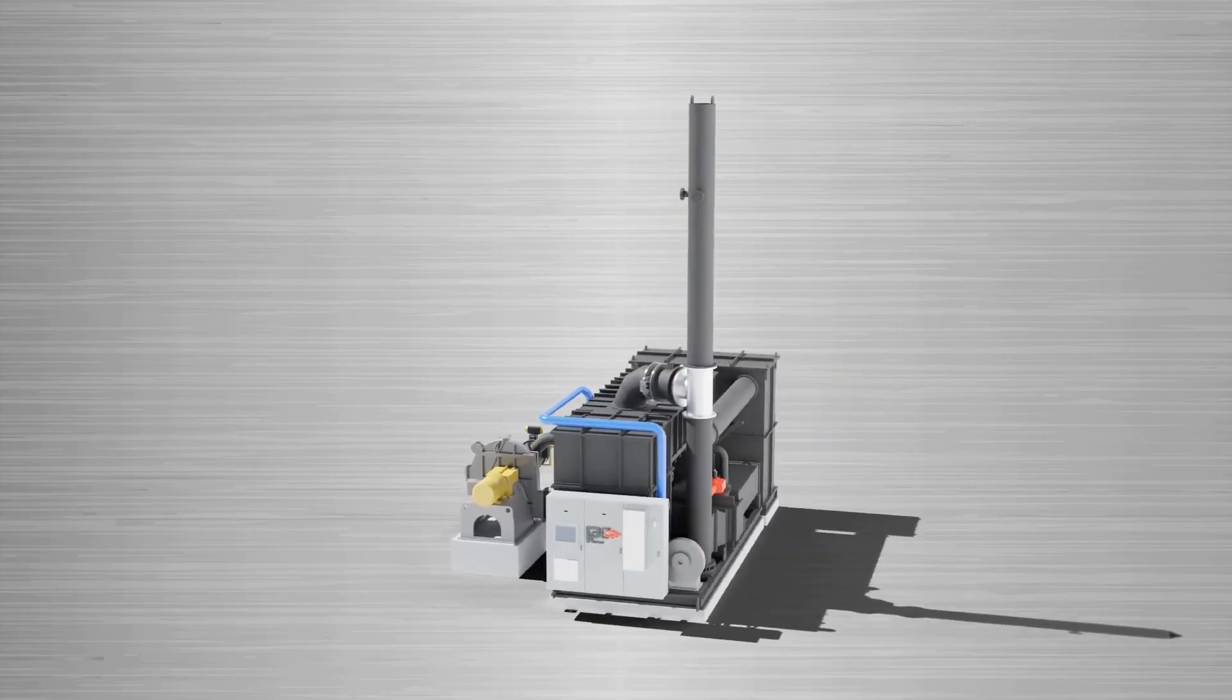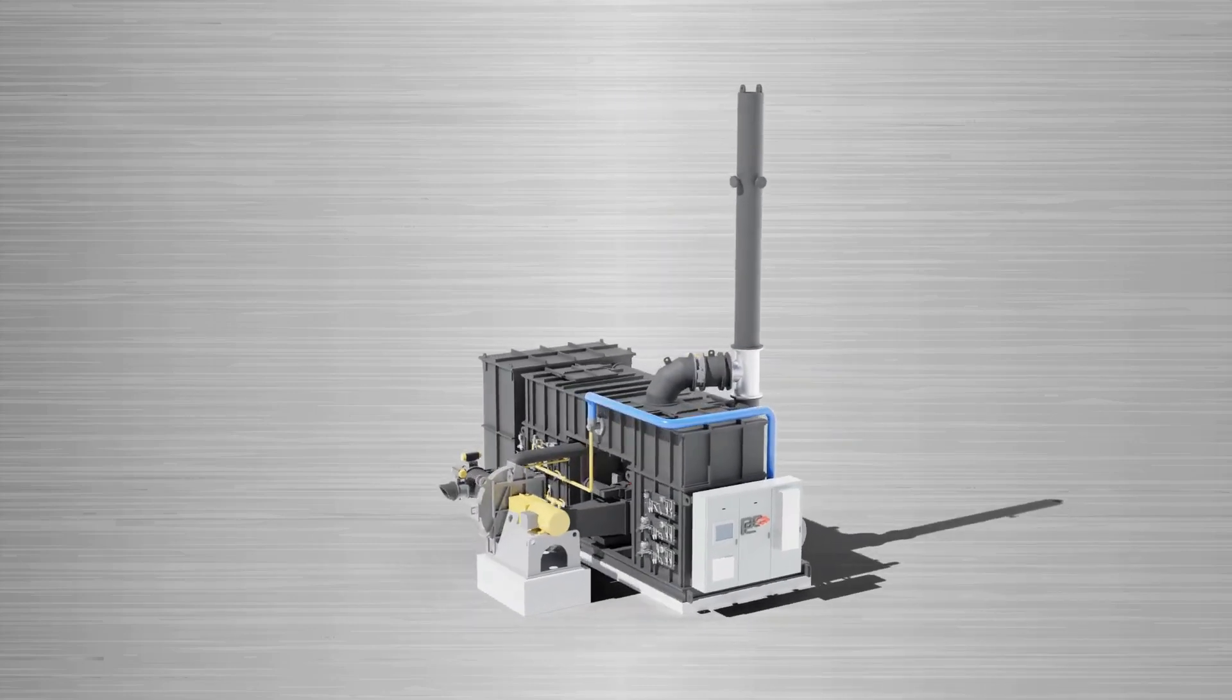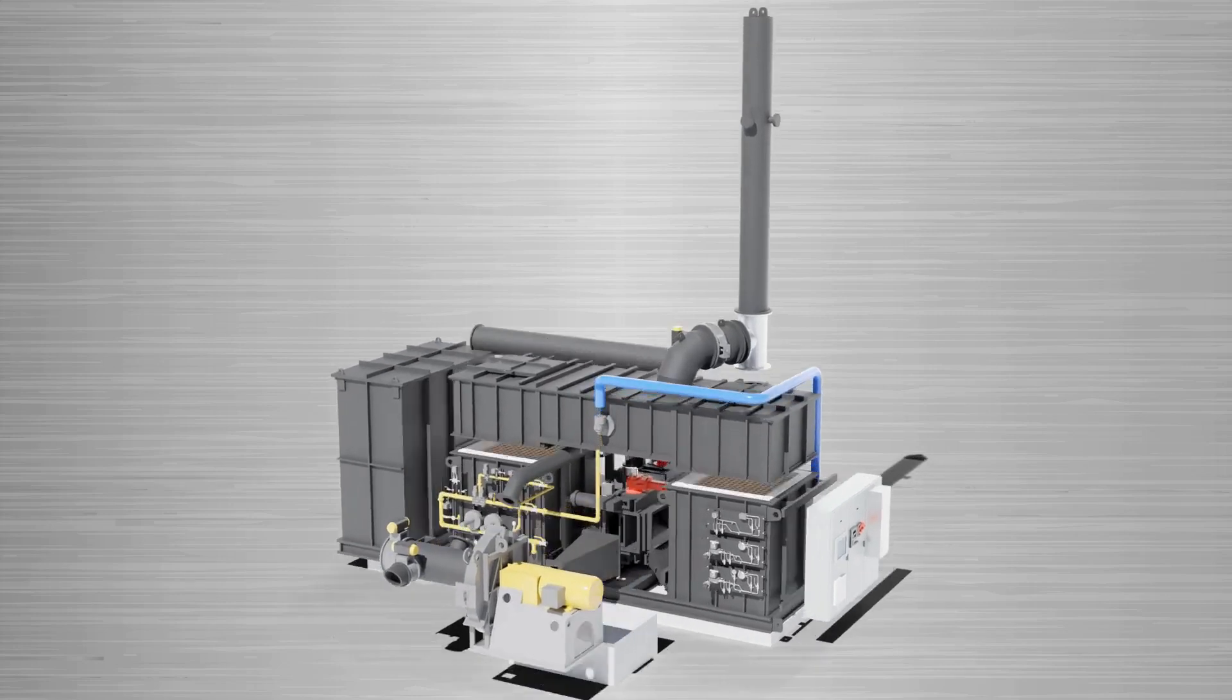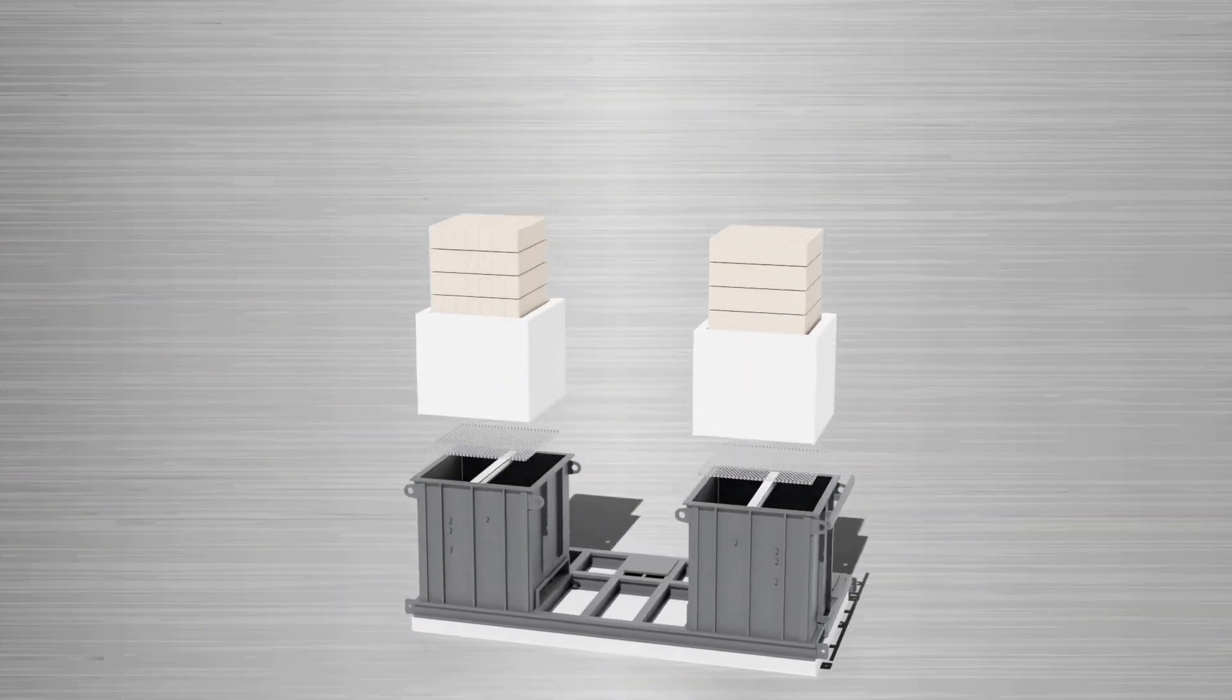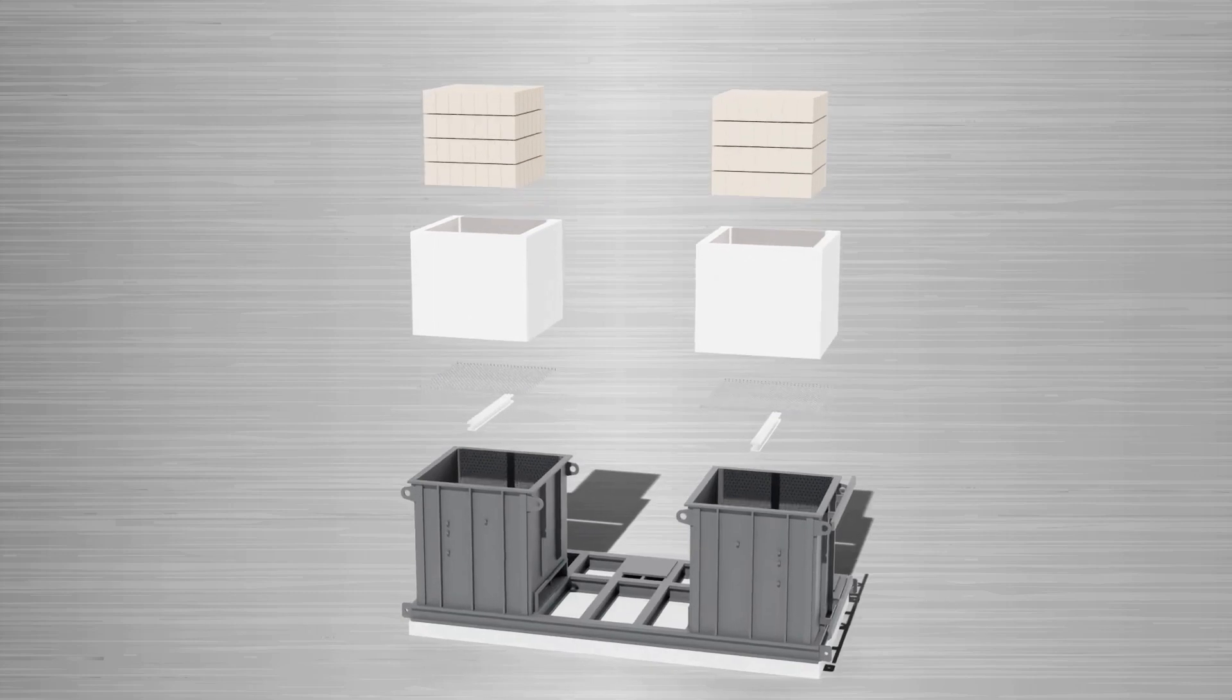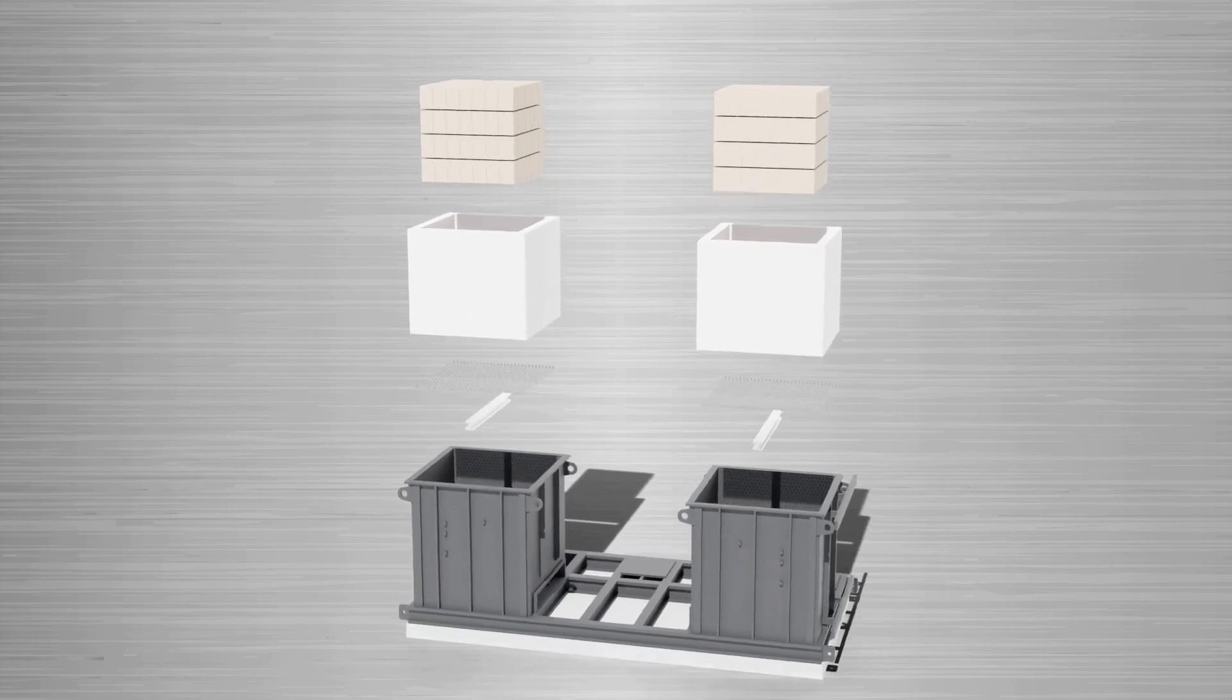Let's take a look at the components and operation of PCC's Quick Switch two-chamber regenerative thermal oxidizer. The system achieves 97% thermal energy recovery by storing heat in ceramic media. The white material is ceramic fiber insulation which maintains a safe external vessel temperature.